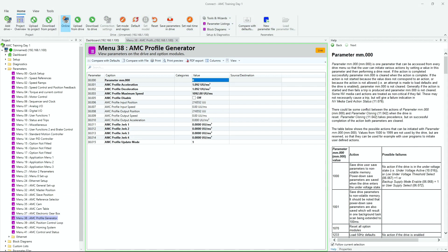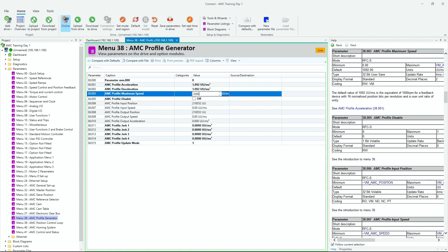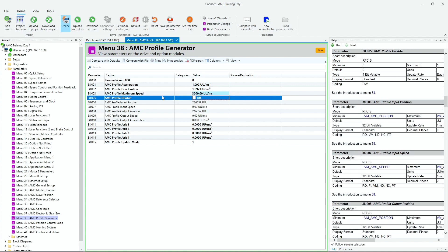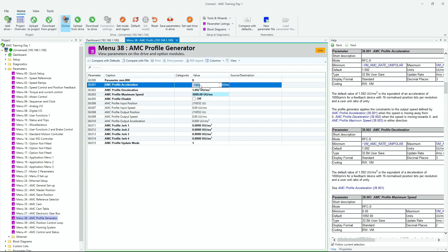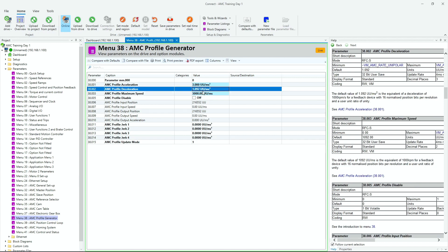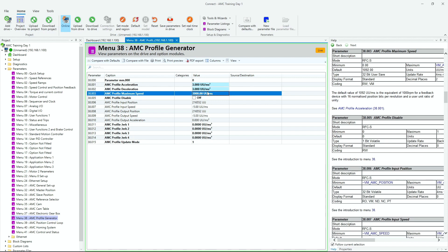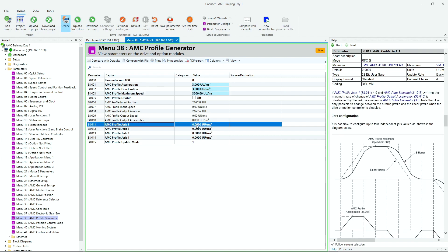In Connect, the speed becomes 3000, acceleration and decel become 3, and jerk parameter 38-11 becomes 0.03 — just a single value applied to all segments. The Connect help tab shows the graphics for these parameters. Now I'll open CT Scope and run the motor to see the result.